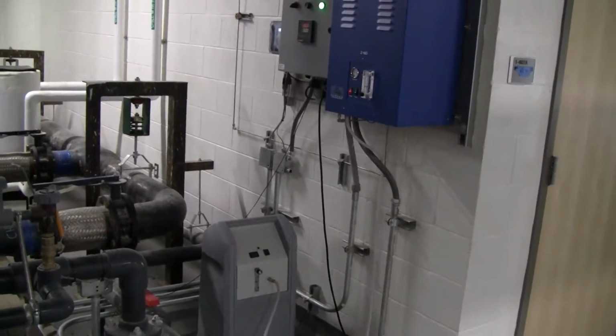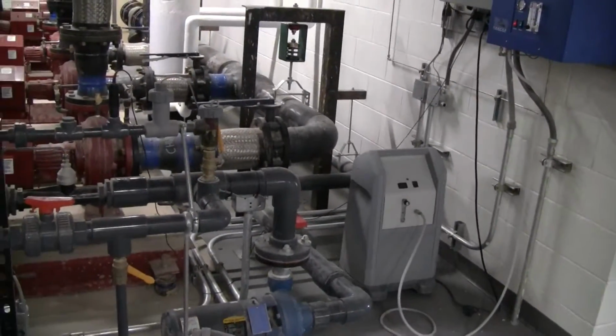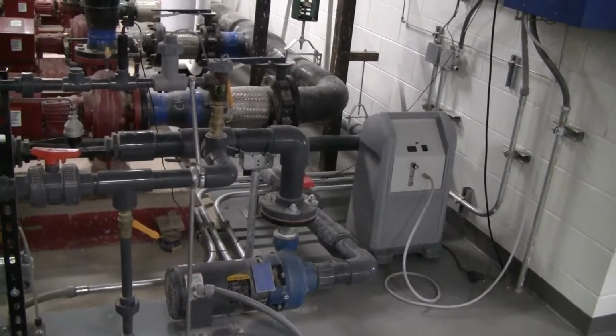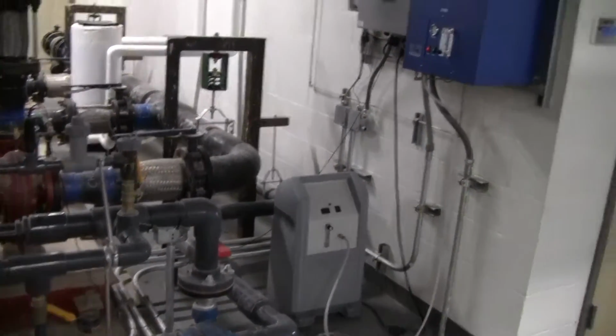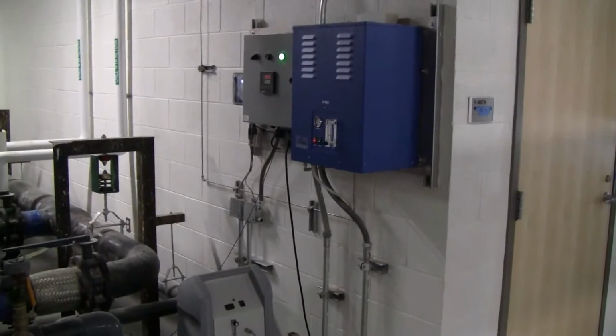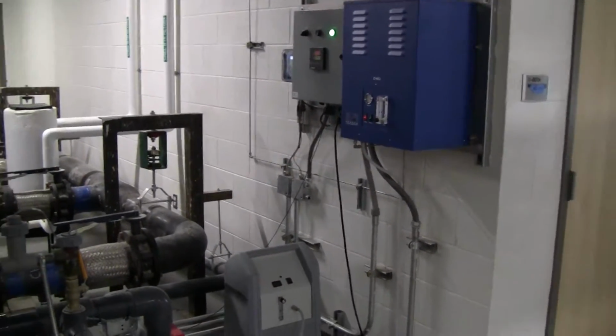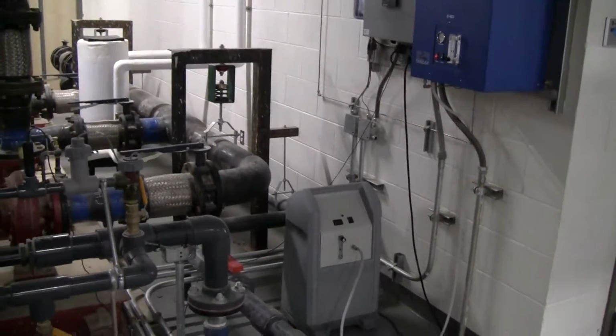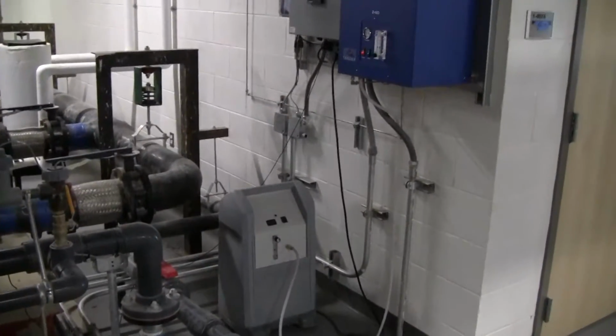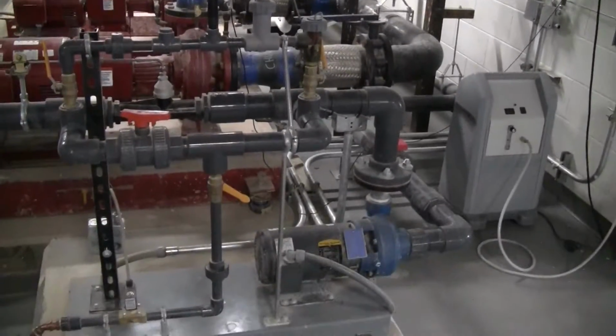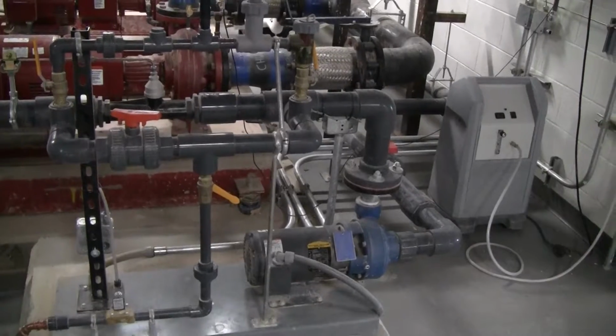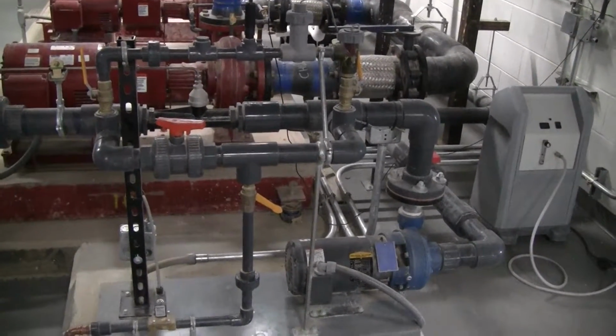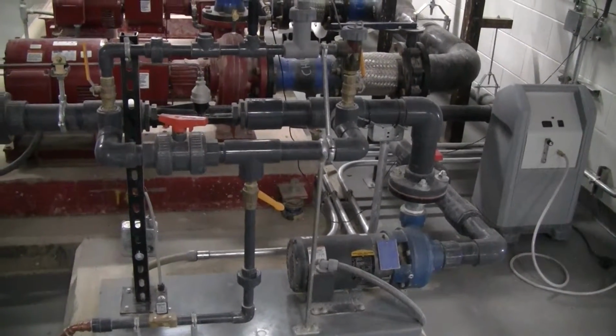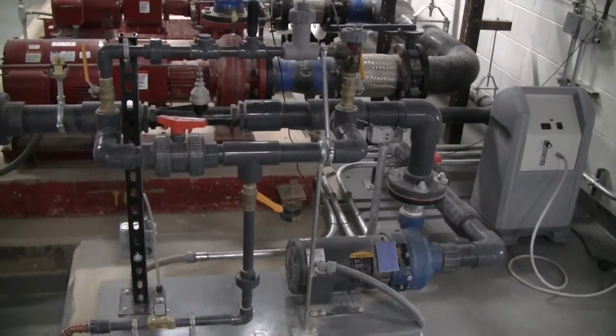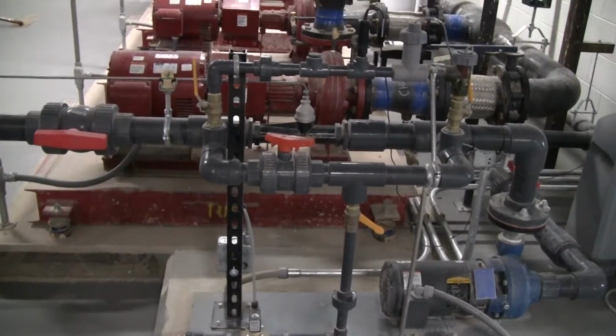This is an overview of the CleanStream's treatment system for cooling towers. This is a CS 800 on an 800-ton cooling tower. It consists of two sections: the water side and the gas side. On the water side, we pull water out of the cooling tower, circulate it through our sample rack, monitoring it, venturing the gas into the water, and sending it back into the cooling tower as treated.